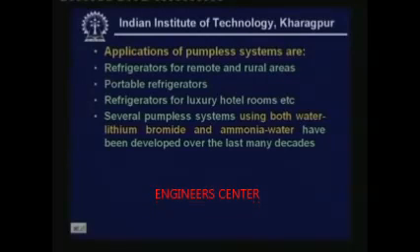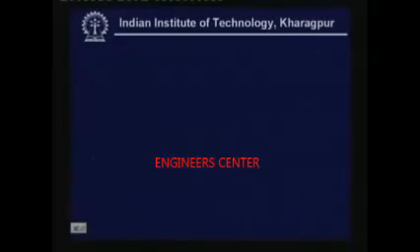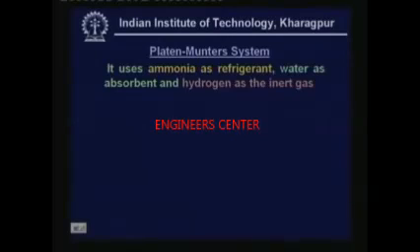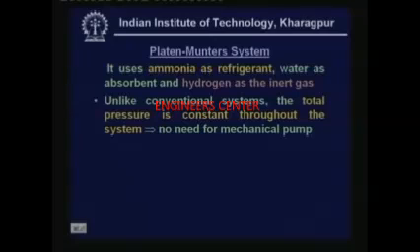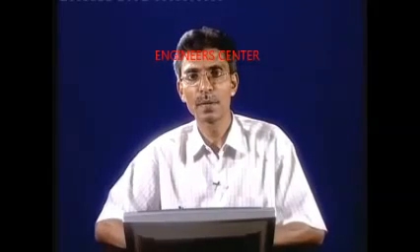There are several pumpless systems using both water lithium bromide and ammonia water, and people have been working on these for many decades. The most popular one is the Platen-Munters system, also known as the triple fluid vapor absorption refrigerant system. This system uses ammonia as refrigerant, water as absorbent, and a third fluid - hydrogen - as the inert gas, which is why it is called a triple fluid system. Unlike conventional systems, the total pressure is constant throughout, so no compressor, pump, or expansion valve is required.